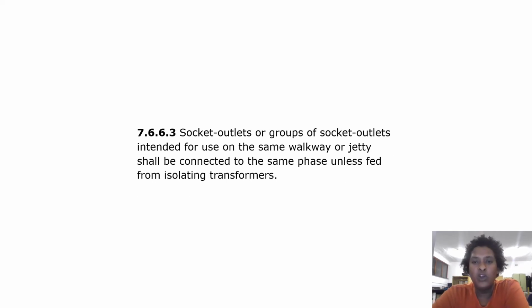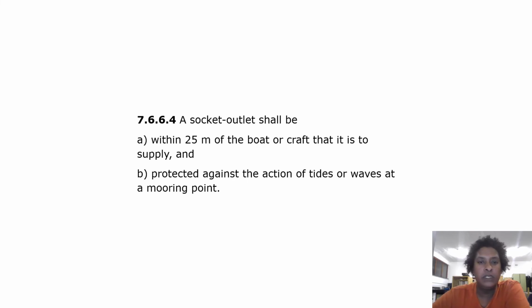Socket outlets or groups of socket outlets intended for use on the same walkway or jetty shall be connected to the same phase unless fed from isolating transformers. A socket outlet shall be within 25 meters of the boat or craft that it is to supply and protected against the action of tides or waves at the mooring point.